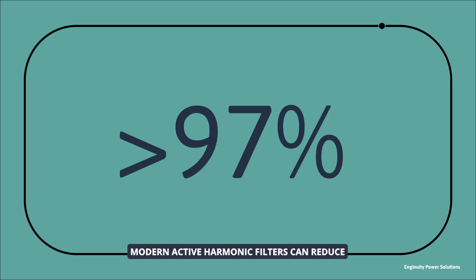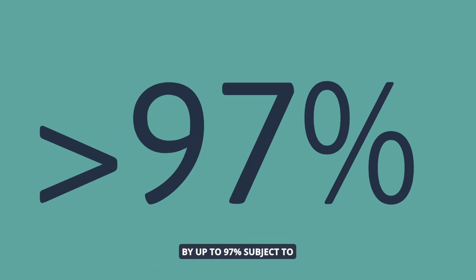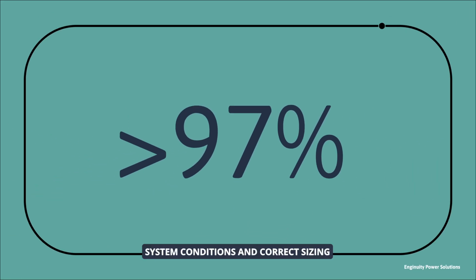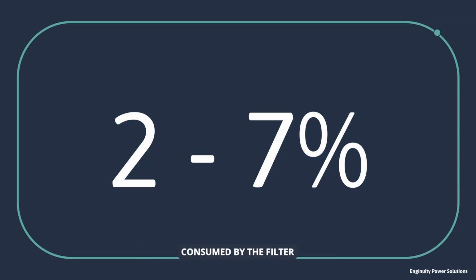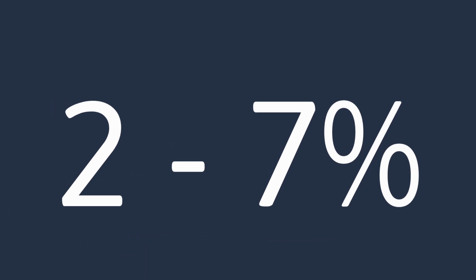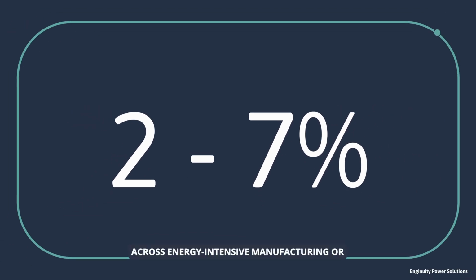Modern active harmonic filters can reduce harmonic distortion by up to 97%, subject to system conditions and correct sizing. That level of correction significantly improves system performance and stability. Even after accounting for the energy consumed by the filter itself, facilities often see a net energy saving of between 2 and 7%. Across energy-intensive manufacturing or infrastructure operations, that translates into meaningful cost reduction. For finance leaders, it strengthens the investment case. For ESG leaders, it delivers measurable efficiency gains.